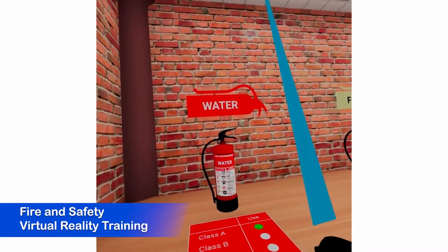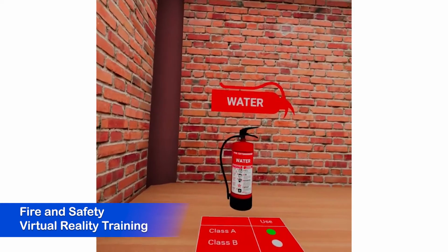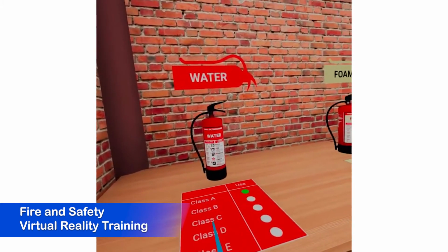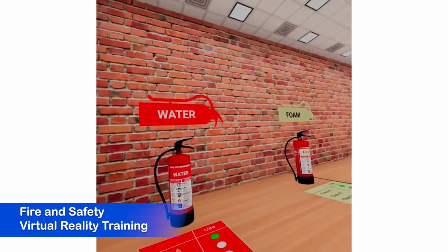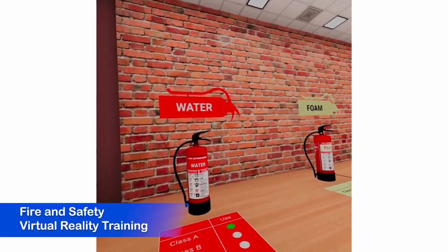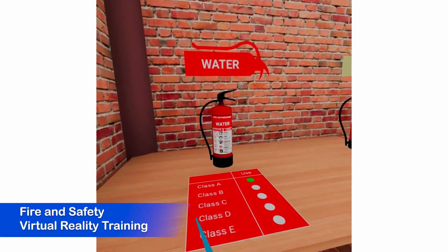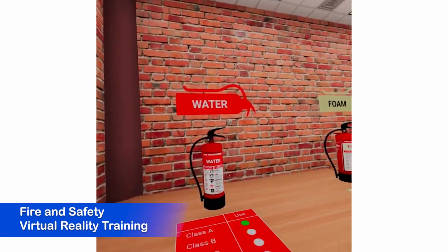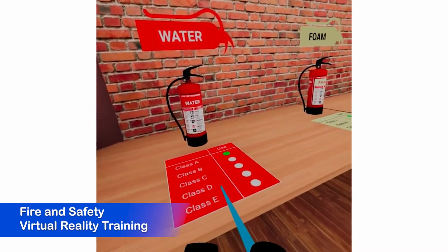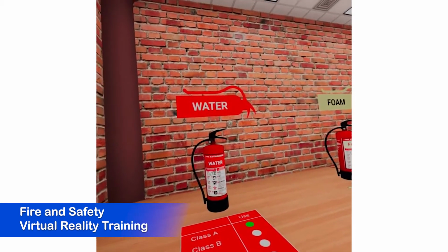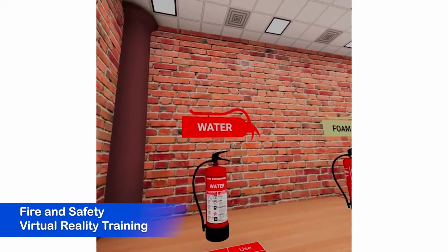Water extinguishers are one of the most cost-effective ways to fight Class A fires, those fueled by solid materials such as paper, wood and textiles. All water extinguishers have a red label. There are 4 different types of water extinguishers also: water jet, water spray, water with additives and water mist or fog.